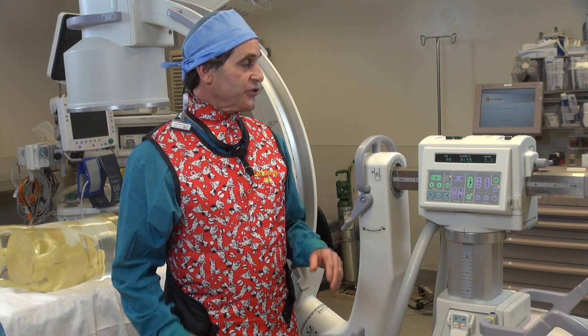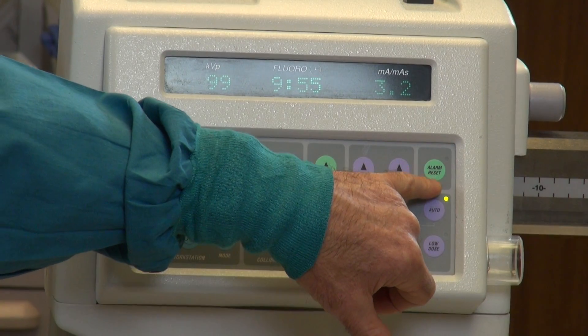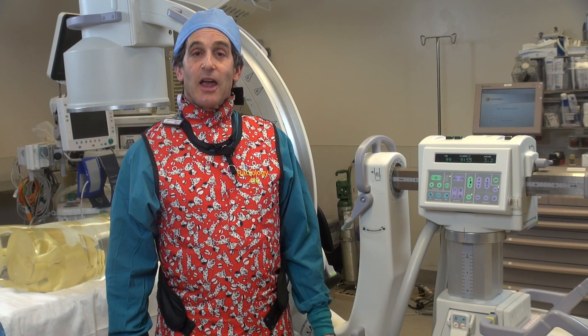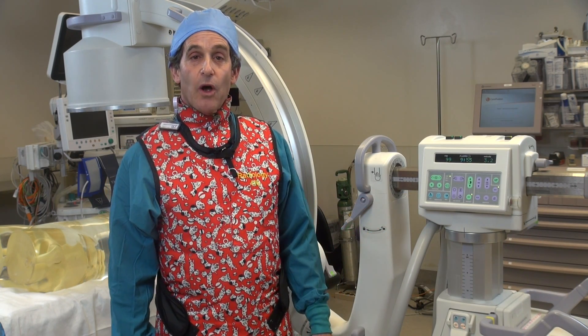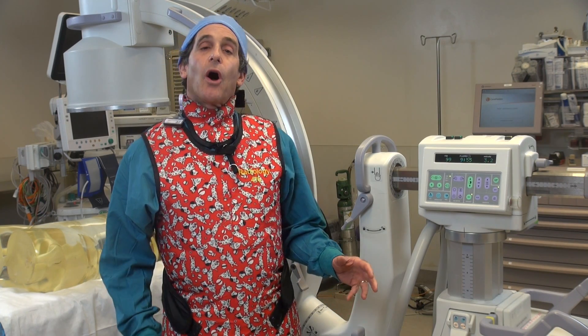The rule is at every five minutes an alarm's going to go off, and it's going to stay going on like that until somebody hits the alarm reset button and turns it off. Or if there's an automatic reset, it's going to go for two seconds and then automatically reset itself. All of the equipment we have here at our hospital are all manual, and somebody has to actually turn them off.